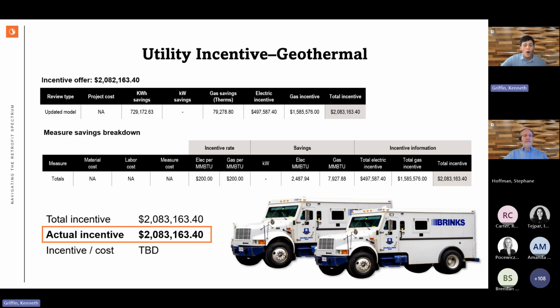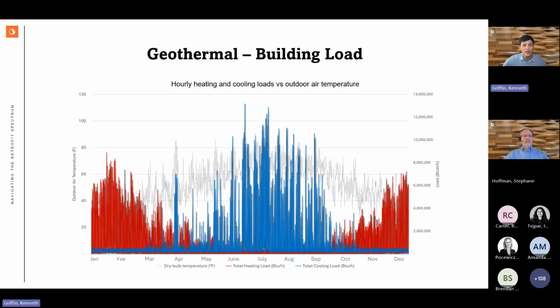While we did this analysis, we were able to provide our geotechnical consultant, PW Grosser, with the building loads. They were then able to calculate the ground source temperatures for their design, seeing what load was going into the ground so they could determine what was coming out, calculating the temperatures hourly based on our hourly load data. So we gave them cooling and heating load and our outdoor temperature.